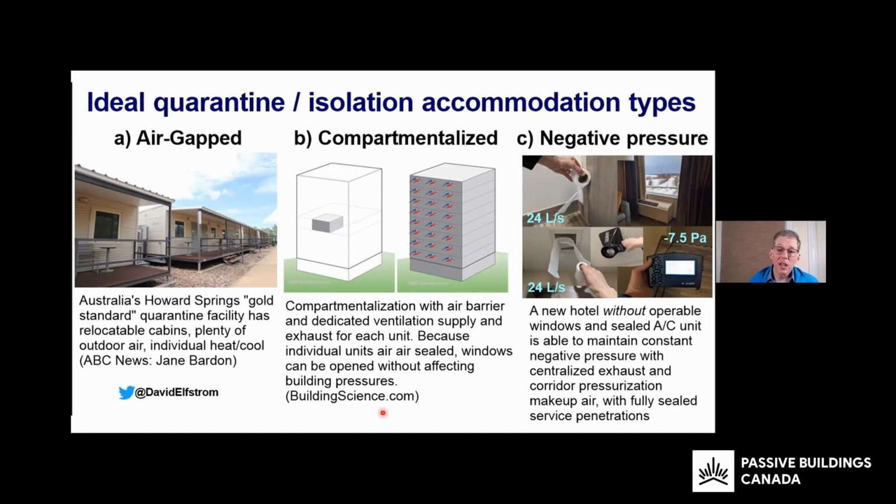And that's been done for designing hospital systems as well. In the standard for hospitals, it's a minimum level of outdoor air changes, and then a total number of equivalent outdoor air or equivalent air changes, usually through a MERV 13 filter and above. And yeah, there's the filtration. To get those higher levels, just like insulation, you're getting diminishing returns as you add more and more. You have to keep doubling the ventilation rate to double the air changes per hour, or to further halve the concentration in a room. So filtration definitely helps save energy that way. And then upper room ultraviolet can achieve those really, really high levels of disinfection very quickly.